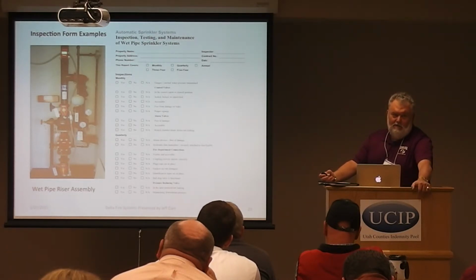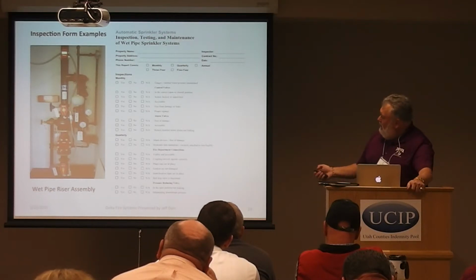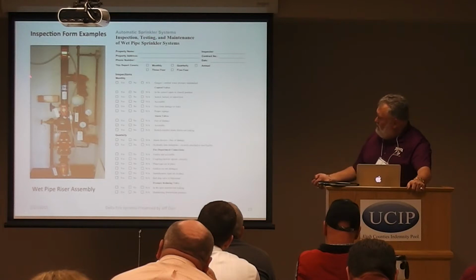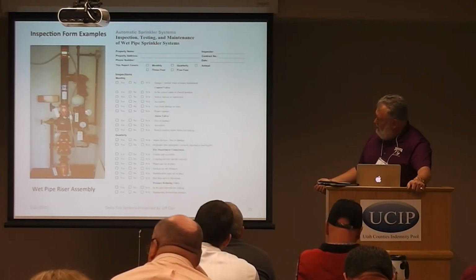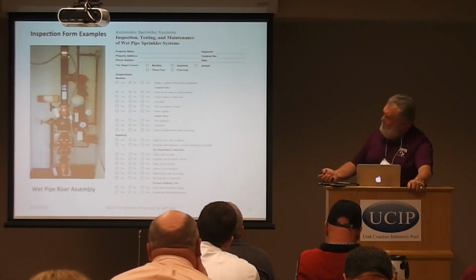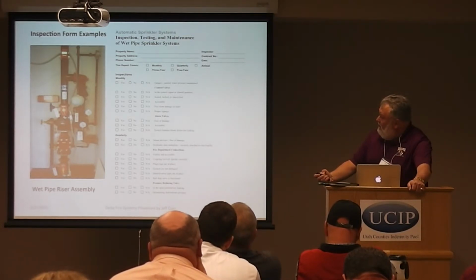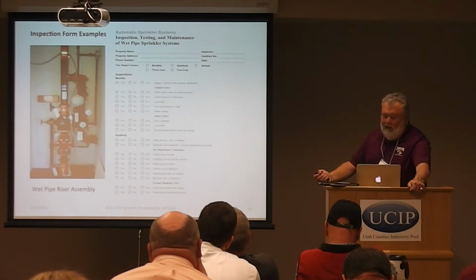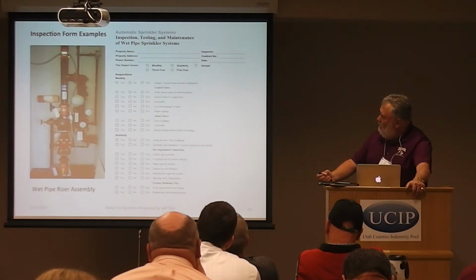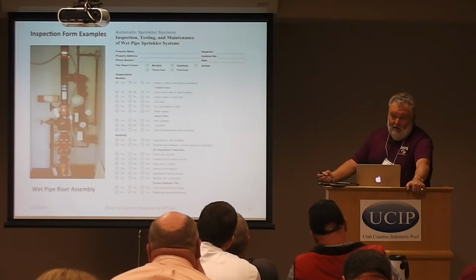So they want to make sure that you can't close it down too quick and cause problems. But in addition, you can quickly see that the gauges are indicating approximately the same pressures. I know you can't really read it from there, but if you get that bottom gauge shut down and the top gauge would have pressure locked in it because of the check valve part of this, it would give you an indication that your water supply is shut off.